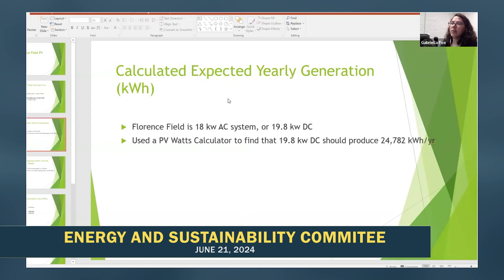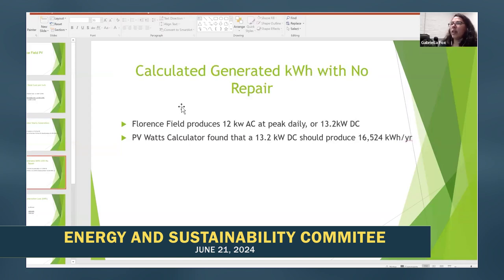Then we calculated the expected yearly generation. Florence Field is an 18 kilowatt AC system, or 19.8 kilowatts DC. We used a PV Watts calculator, which uses the DC figure, and found that the 19.8 kilowatt DC system should produce 24,782 kilowatt hours per year. As of right now, Florence Field produces roughly 12 kilowatts AC at peak per day, or 13.2 kilowatts DC. Using the PV Watts calculator, the 13.2 kilowatts should produce 16,524 kilowatt hours per year.